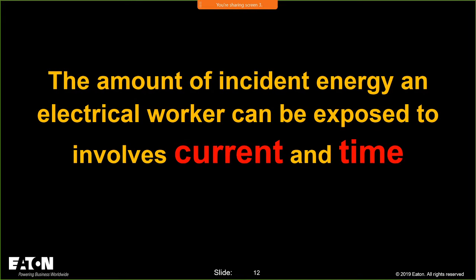And the amount of energy that we release is dependent upon two key factors. There are other factors, obviously, but there are two key factors that will impact how much energy we project, and that is current and time. It's how much arcing current I let flow and how long I let it persist. And that is a very critical and important thing to remember from a hazard awareness perspective.